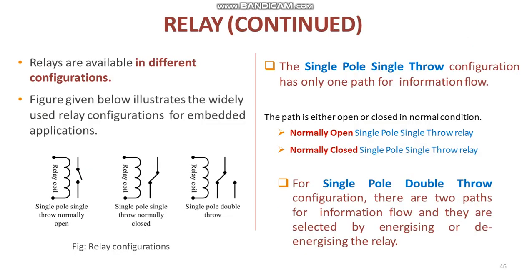Relays are available in different configurations as shown in the diagram. The single pole single throw configuration has only one path for information flow; the path is either open or closed in normal condition. For a normally open SPST relay, the circuit is normally open and it becomes closed when the relay is energized. For a normally closed SPST relay, the circuit is normally closed and it becomes open when the relay is energized. For the single pole double throw configuration, there are two paths for information flow and they are selected by energizing or de-energizing the relay.